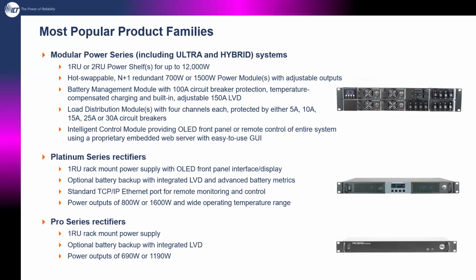Battery management—we're connecting either 1 or 2 backup battery strings to provide backup power. We've got 100 amp circuit breaker protection on these units, and the low voltage disconnect will take up to 150 amps.